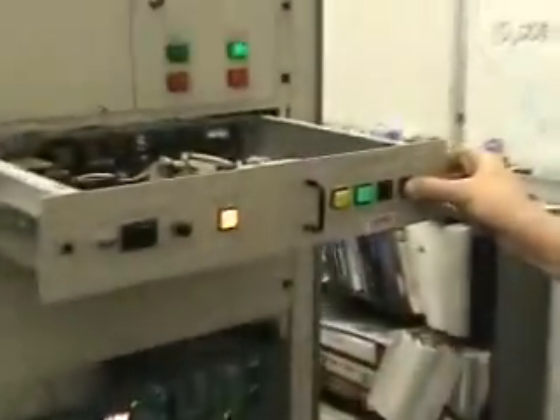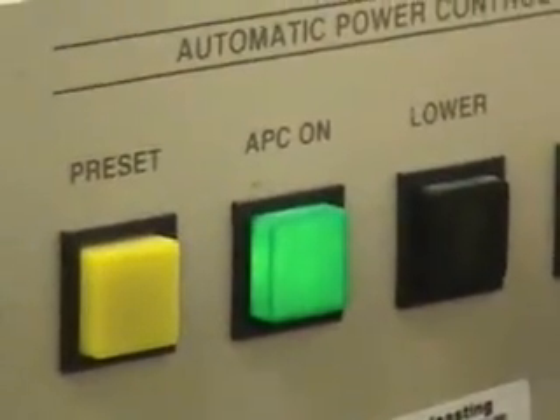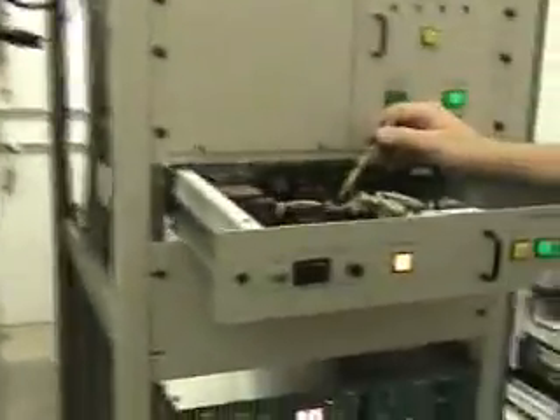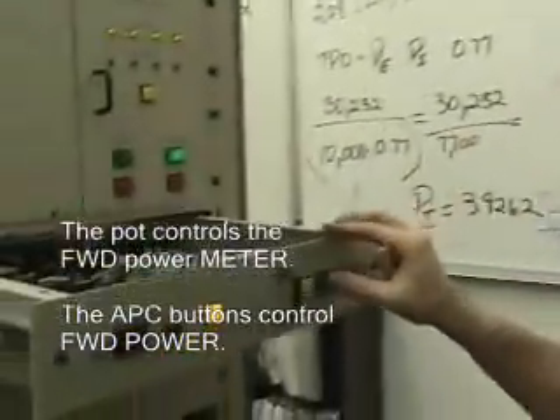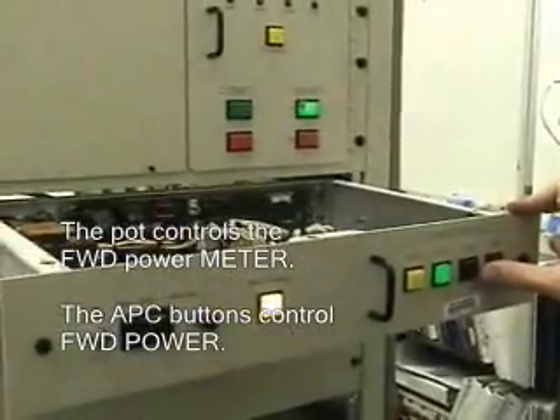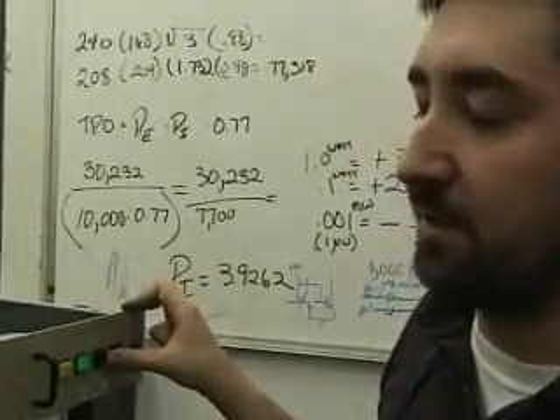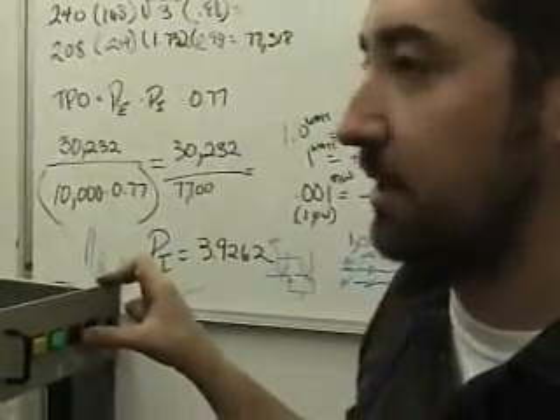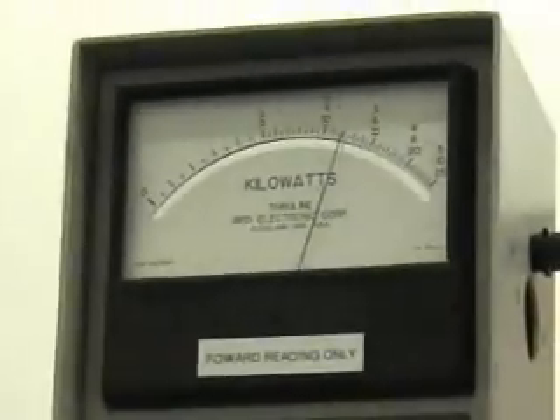Make sure APC is on when you're doing it, otherwise you're not programming it. You want to program for 100% power, so you alternate between this forward power pot and your APC. So you're going to be turning your APC off, moving your power to where you want it, turning APC on, and holding down raise or lower. It's a little finicky to get it just right, but if you play with it back and forth between the two, you'll get your meter calibrated. You have to have an inline watt meter, inline section, to calibrate this correctly.